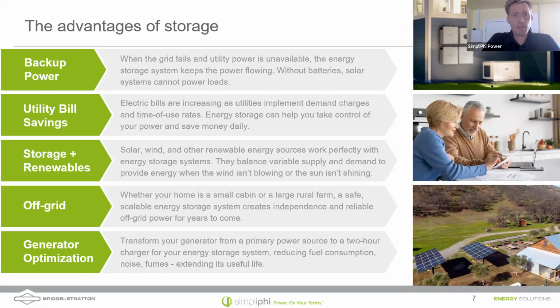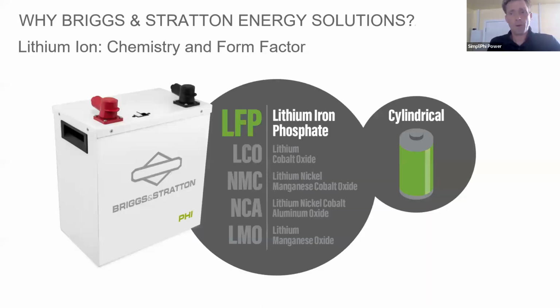Storage and renewables offer this ability to save that energy during the day and discharge at nighttime when you need it. Of course, the off-grid market, you don't have access to grid, and so you can have power with storage in off-grid markets. And we can even optimize generators. So if you are in an off-grid situation and are looking to run your generator a little bit less, use less fuel, run it at the peak efficiencies, you can do so. If you have batteries, you can run your generator for a short time, charge up those batteries, and then discharge those batteries until they need charged again. And so there are a lot of reasons to have storage. We're going to talk about how that actually functions and how the battery management system plays a big role in healthy functioning systems.